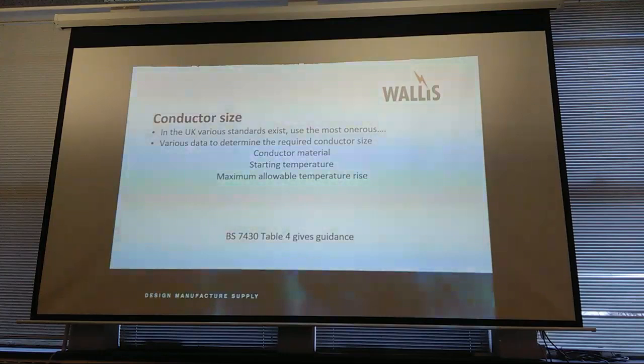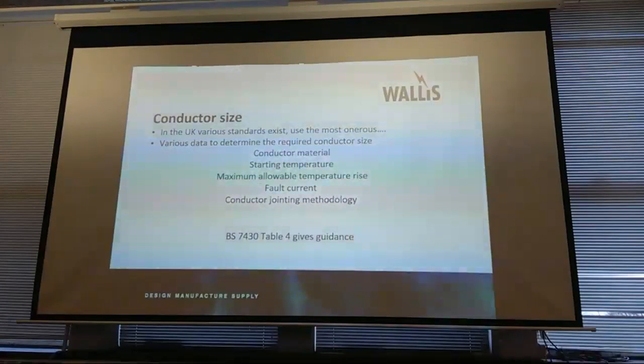So you can push that copper very, very hard, but obviously then you've got to be aware of what is around that copper under fault conditions. You're then obviously going to know the fault current. The conductor jointing methodology will make a massive difference as well. Whether you're exothermically welding a joint, bolting a joint, or clamping a joint, the hierarchy tends to be an unbroken piece of copper, a braze, an exothermic weld, a clamp joint, a bolted joint. And that tends to be where we will get to. That's not documented anywhere. That's just us as a manufacturer selling all these things. When we get in a type test, that tends to be how we see it come back.